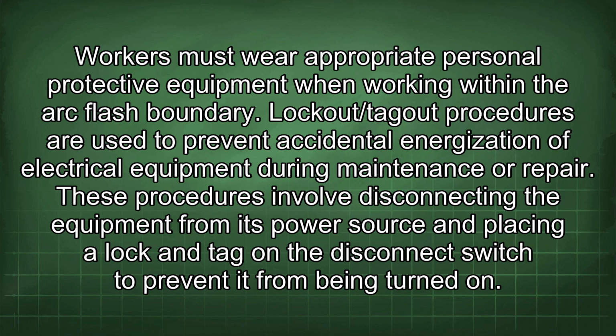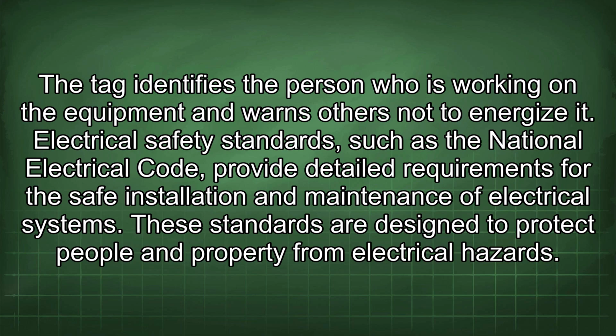Lockout/tagout procedures are used to prevent accidental energization of electrical equipment during maintenance or repair. These procedures involve disconnecting the equipment from its power source and placing a lock and tag on the disconnect switch to prevent it from being turned on. The tag identifies the person who is working on the equipment and warns others not to energize it.